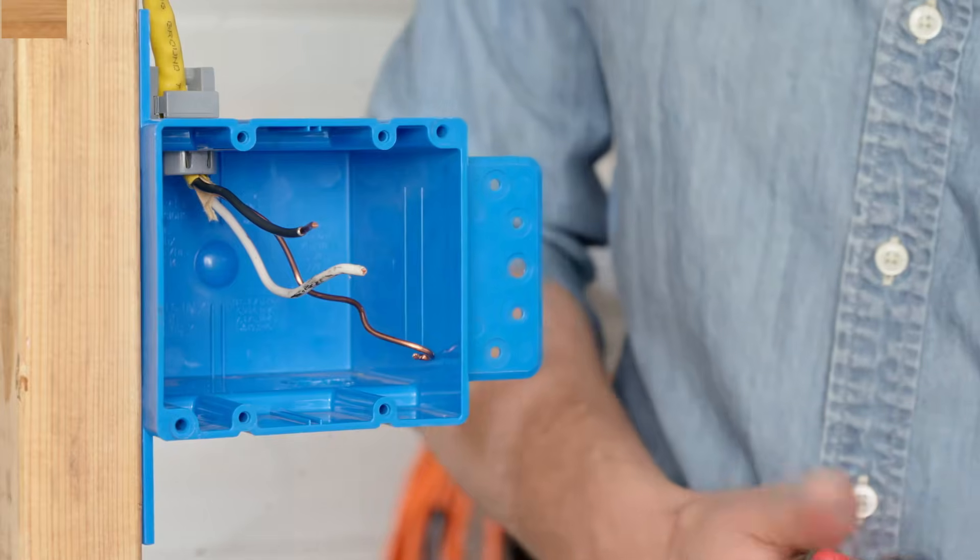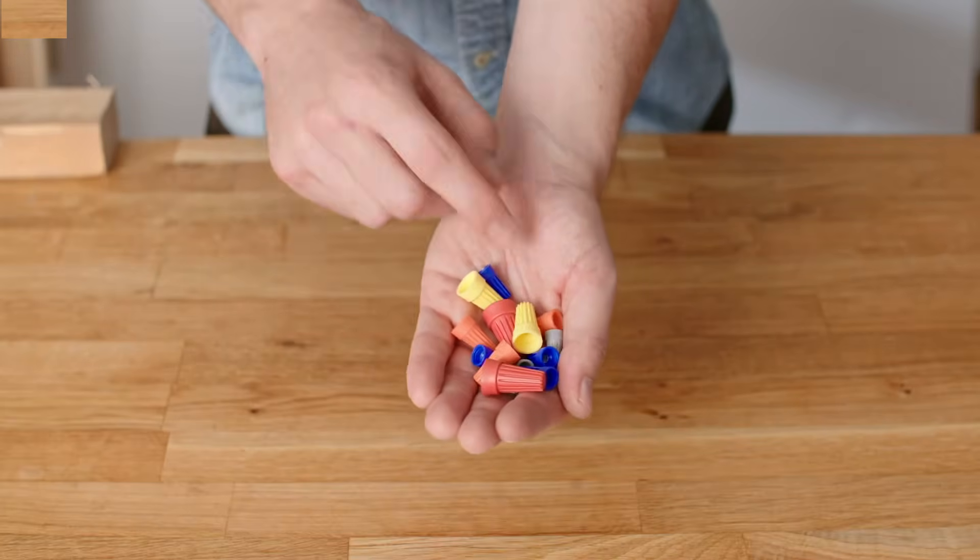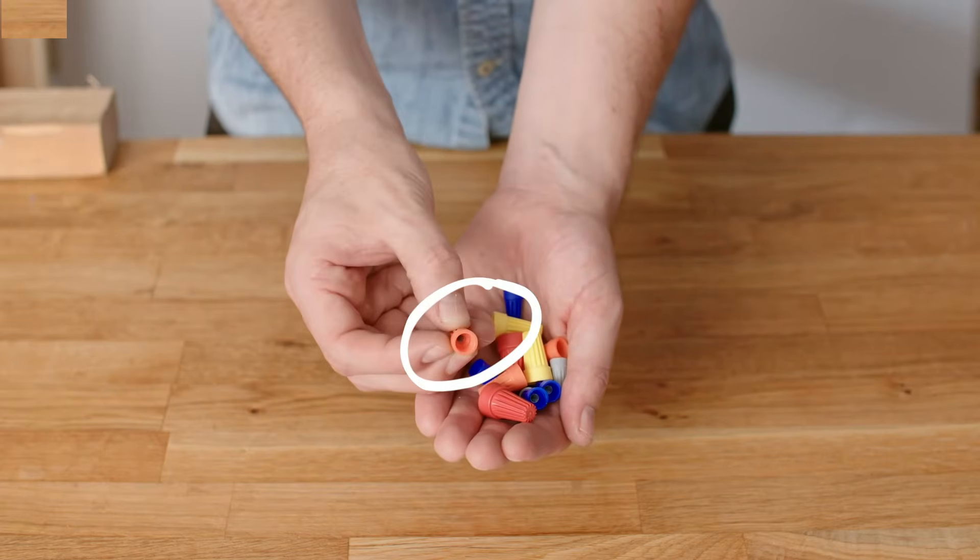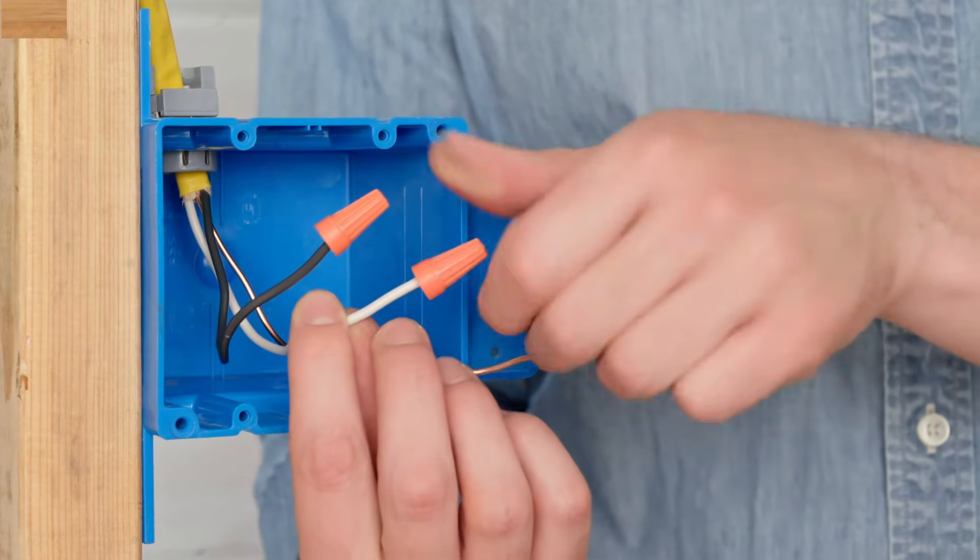Now twist on a plastic wire nut to cap each wire. Use the appropriate size wire nut to cap your wire. The smallest nuts in most standard variety packs work best for 14 gauge and 12 gauge wire. Turn the wire nut clockwise as tight as you can get it by hand.